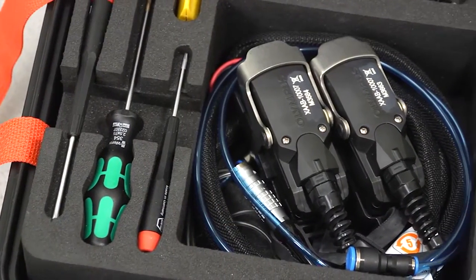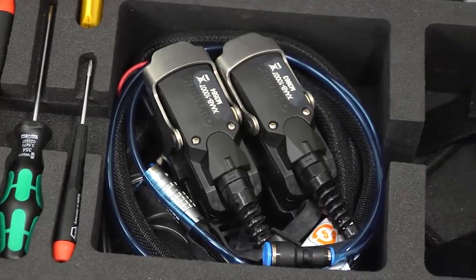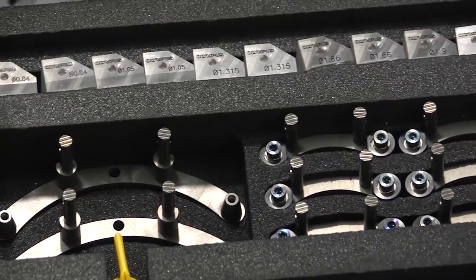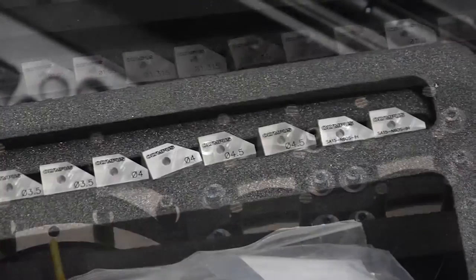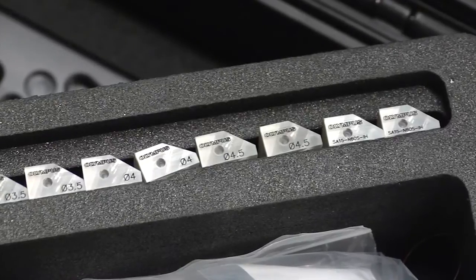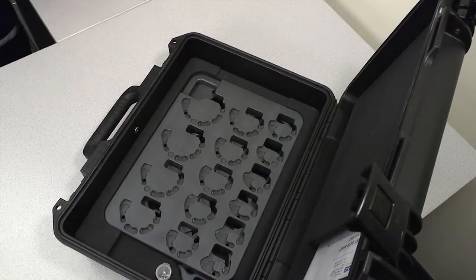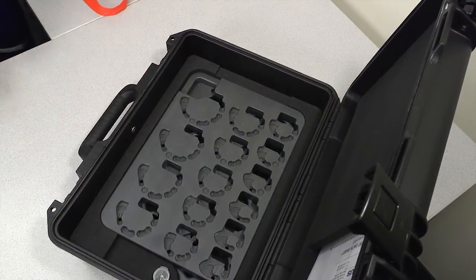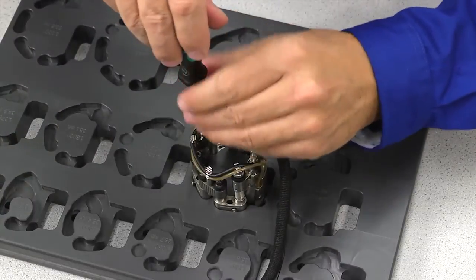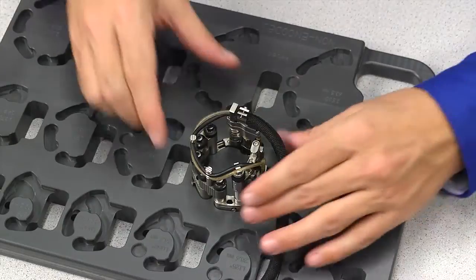The Cobra kit comes with everything needed for the OmniScan to perform one or two-sided weld inspection, including contoured wedges that cover the ANSI piping range from 0.84 to 4.5 inches or 21 to 114 millimeters. Templates included in the kit are used to configure the scanner for different pipe diameters and to ensure proper tension for the guide wheels and encoder for smooth consistent scanning in both directions.